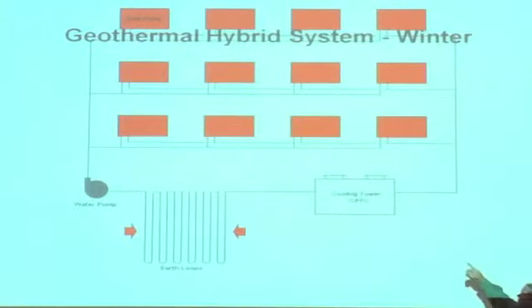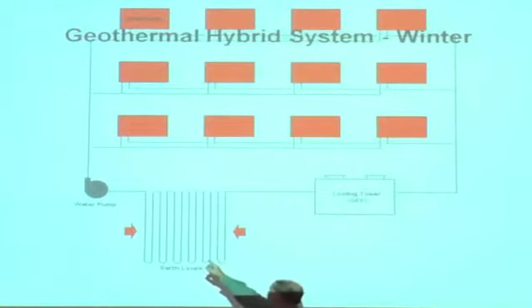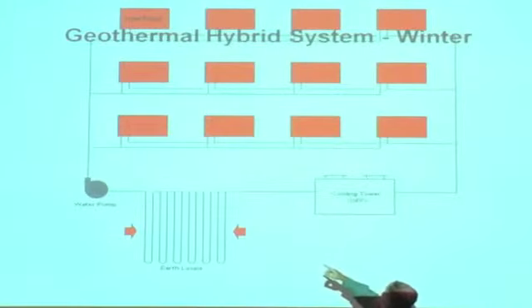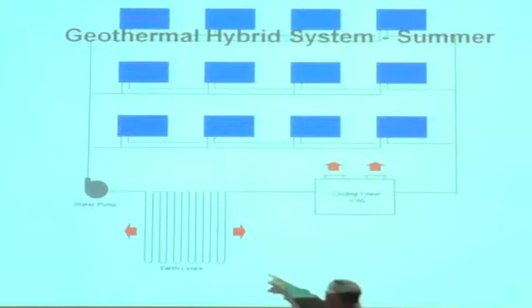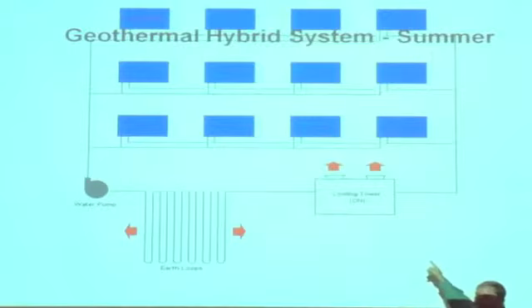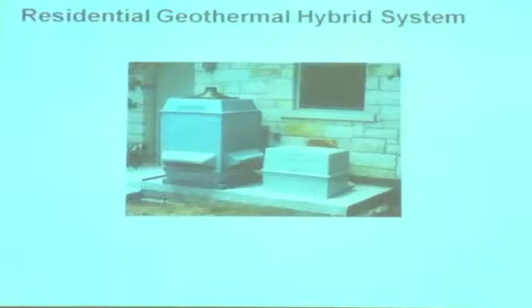So a hybrid system, if you get a really large application, this is typically the way you do it. You size the ground loop to provide 100% of the heat, and for cooling, you put enough heat in the ground to get you through the winter, then reject the rest. From a capital cost standpoint, if you've got a whole lot of cooling going on, this is one of the most cost-effective ways to do it.